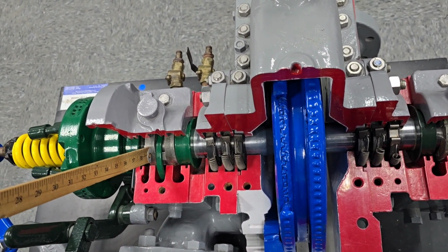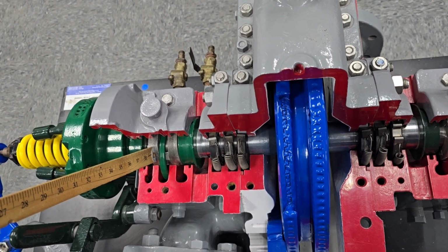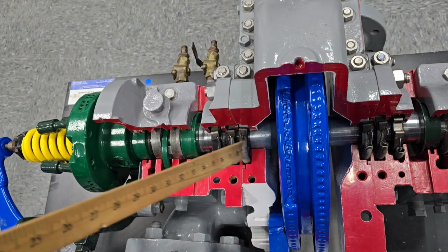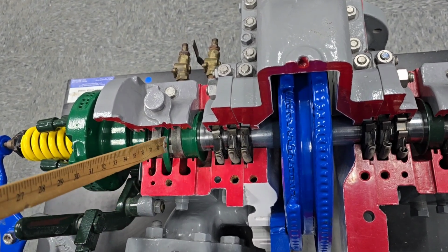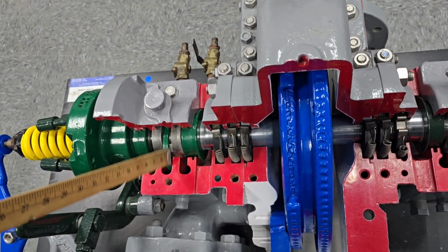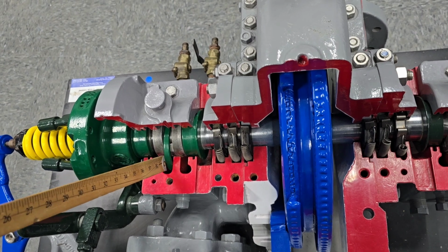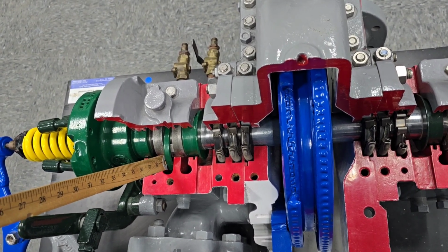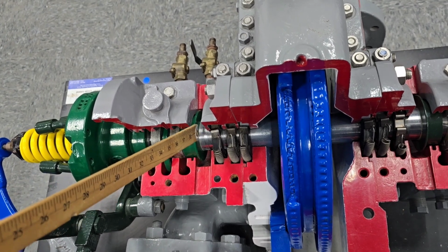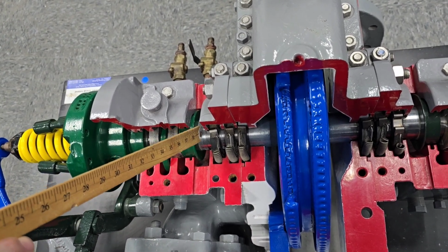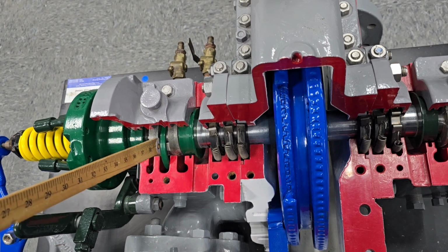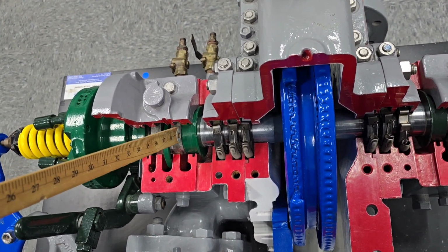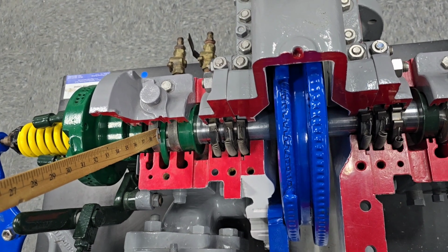The bearing right here is going to be called the axial bearing or the thrust bearing, controlling the movement of the shaft in this direction. The slinger ring, located right here, is going to sit loosely in the oil, the lubrication you have in the bearing housing, and as the speed of the shaft begins to rotate and pick up, this will start to pick up the oil and bathe your bearings and keep them cool.